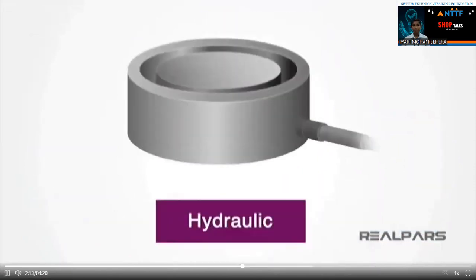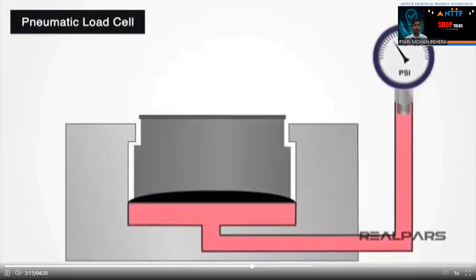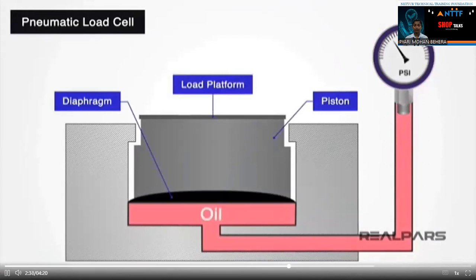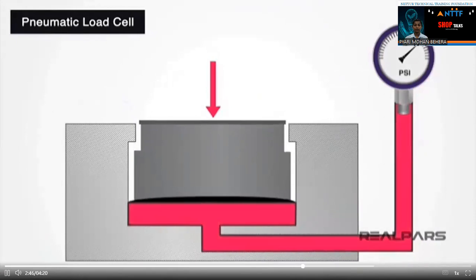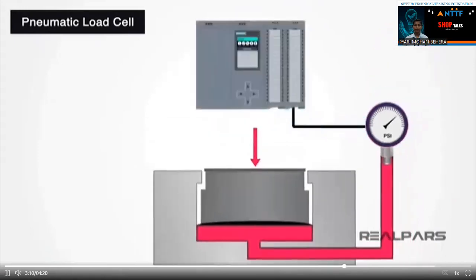Next, let's talk about a hydraulic load cell. The word hydraulic should let us know that this load cell will work by using fluid, whether water or oil. These load cells are similar to pneumatic load cells, but instead of air, they use the pressurized liquid. A hydraulic load cell consists of an elastic diaphragm, a piston with a loading platform on top of the diaphragm, oil or water that will be inside the piston, and a Bourdon tube pressure gauge. When a load is placed on the loading platform, the piston applies pressure to the liquid contained inside it. The pressure increase of the liquid is proportional to the applied force or weight. After calibrating the pressure, you can accurately measure the force or weight applied to the hydraulic load cell. The pressure reading can be read as an analog gauge, or it can be converted into an electrical signal from a pressure sensor.